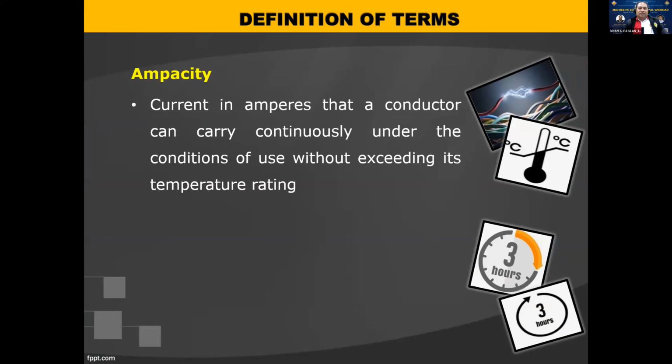No? Yung term na ampacity cannot be found, I don't know ngayon kung meron na ba yan sa dictionary ni Webster, but it's our specific technical term natin yan, no? It's the current in amperes that a conductor can carry continuously under the conditions of use without exceeding its temperature rating. No, so basically, it's the load.